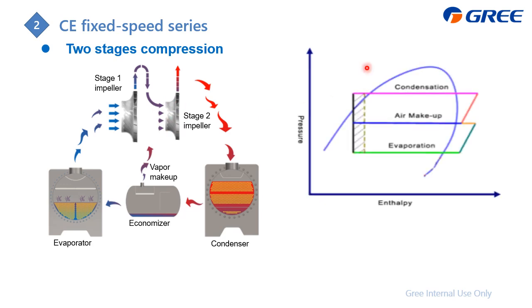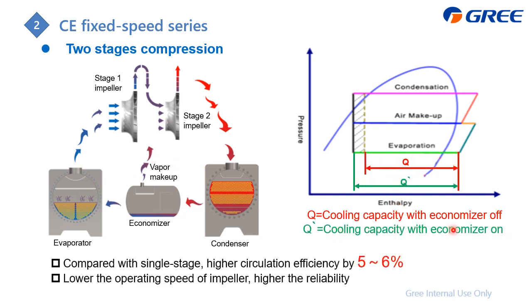And the benefit you can find from this view. This is the cooling capacity, evaporation, and this is the condensation. This is the original with the economizer off, and this one is the economizer on, which means from here we join here, then we can get this additional part. This additional part gives about 5 to 6% higher efficiency. And also for this one, we can lower the speed of the impeller, which means lower compressor RPM. This can raise the system reliability.